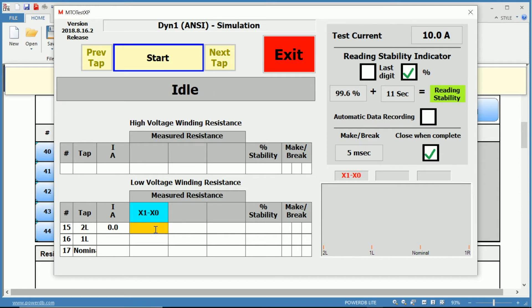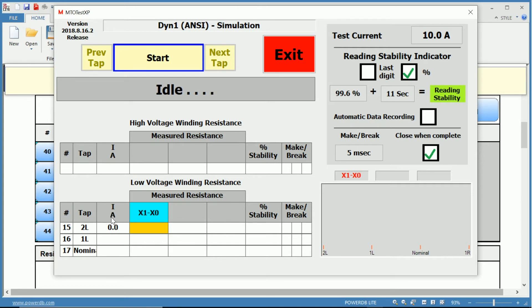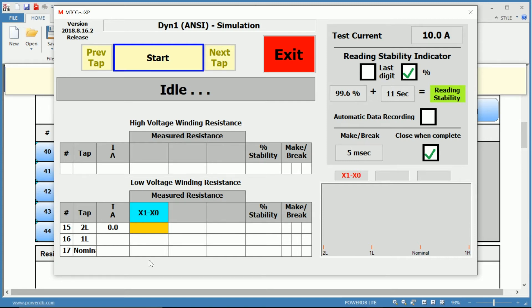That it is ready for us to test the X1 to X0 phase tap two lower, and you can see the orange box is awaiting our measurement. So you have your test number, your actual tap you're testing, followed by the current in which it was used to perform that test, the measured resistance for each of your phases.